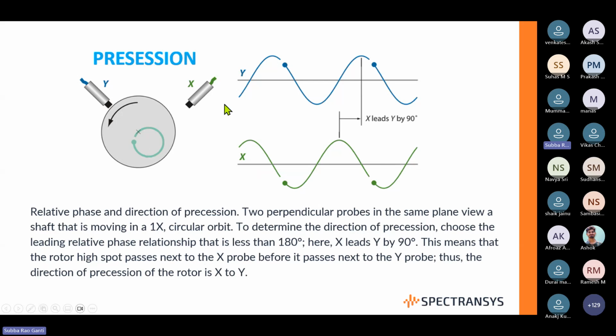Now, when you want to describe the precession of this X and Y probe, I'm starting my journey from the blank and the bright. Because the key phasor is looking at a keyway, the direction of movement of the rotor is from blank to bright - so the rotor is moving in this fashion. When the key phasor is firing, the blank and bright event on the Y probe is at this location, and the blank and bright on the X probe is at this location. This is the starting point for the rotor rotation from our point of view.